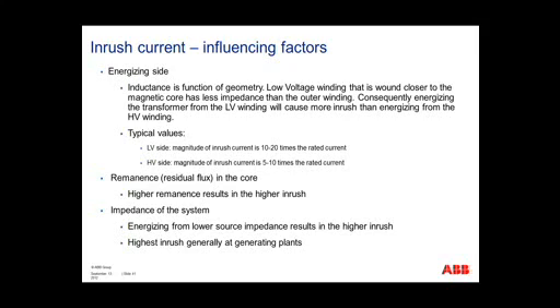What also influences the inrush current? What side you actually energize the transformer on. Since the low voltage winding is closest to the core, if you energize the low voltage winding first, you can typically expect inrush currents of 10 to 20 times the rated current. However, if you energize the transformer on the high voltage side, typical inrush currents are 5 to 10 times the rated current. Remanence: the higher the remanence, or the higher the flux inside the core, the higher the inrush is. Also, the impedance of the system is a contributing factor. Energizing from a lower source impedance results in a higher inrush. Plus, you'll see the highest inrush generally at generating plants.